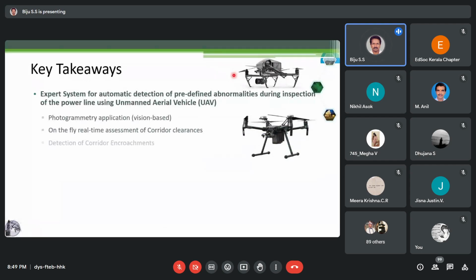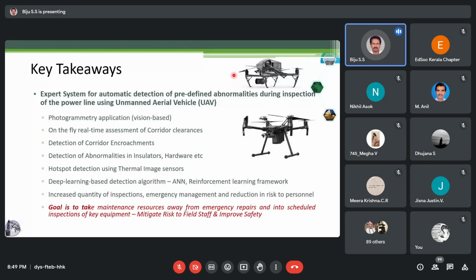The key takeaways are that we can have an expert system for automatic detection of predefined abnormalities during inspection of the power line using UAV. That is the most important thing. Vision-based photogrammetry can be applied for detecting anomalies in the line and for calculating the vegetation clearance. On-the-fly real-time assessment of corridor clearances, detection of corridor encroachments by vegetation, people or buildings, and detection of abnormalities in insulators, hardware, conductor, etc. are possible. Hotspot detection can be done using thermal image sensors. A deep learning-based algorithm can be used for detecting anomalies and predicting system healthiness.